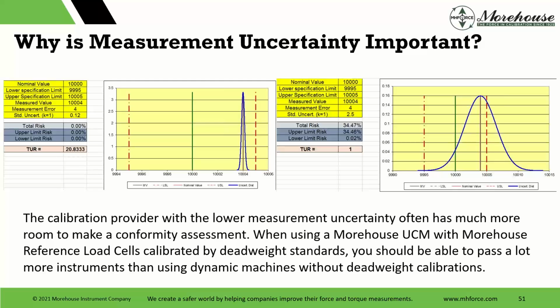Now, on the right, a calibration provider with higher uncertainty does the same calibration. Look at this. Same specifications, much higher uncertainty. They make a measurement at 10,004. If they're not doing conformity assessments or pass/fail, they're going to pass you 34.47% risk. They're just going to give it to you. You're going to take it without knowing.